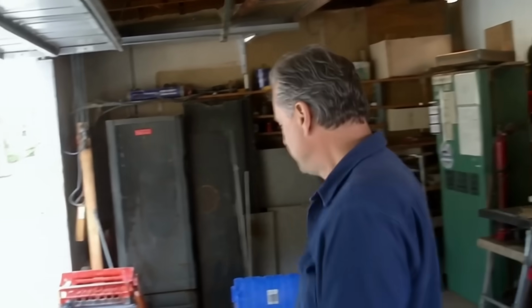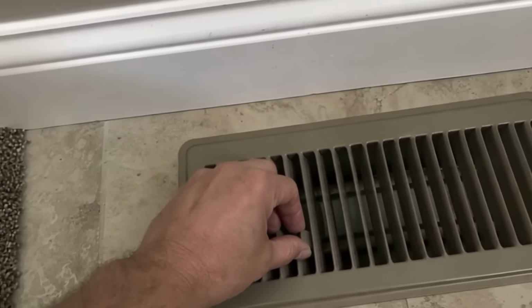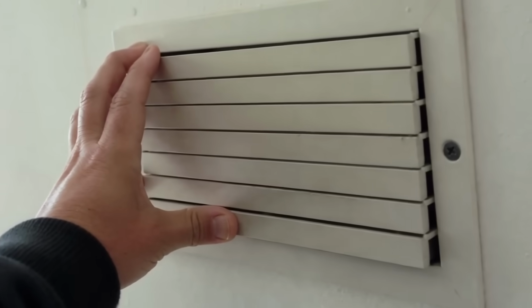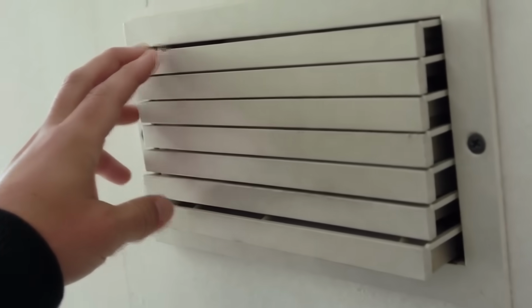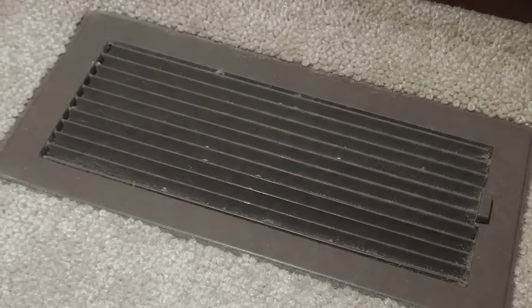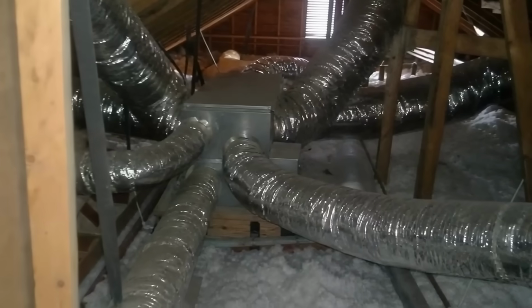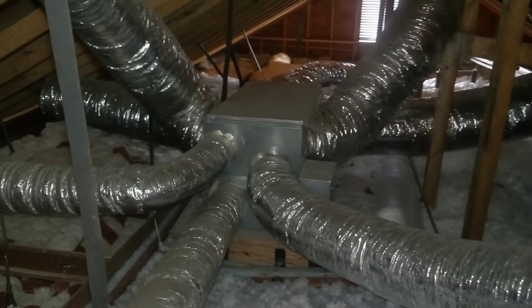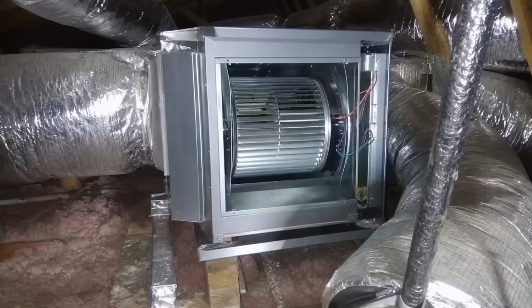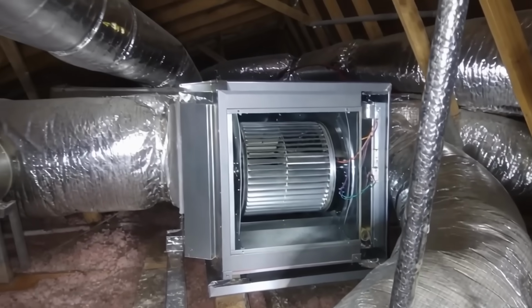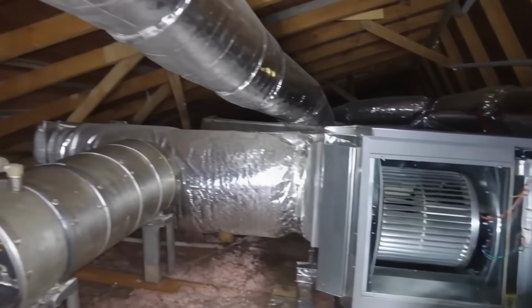Number 2, closing the vents in the rooms you don't use. This one feels like pure common sense. Nobody's in the guest room, so why cool it, right? Shut the louvers, shove the cold air where the people are, save a few bucks. Except that's not what happens. Your duct system isn't a bunch of independent pipes. It's one balanced loop, engineered so the blower pushes a set amount of air and gets a set amount back.